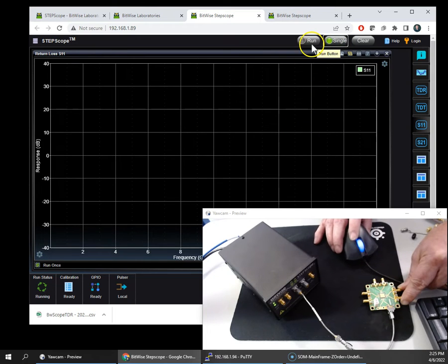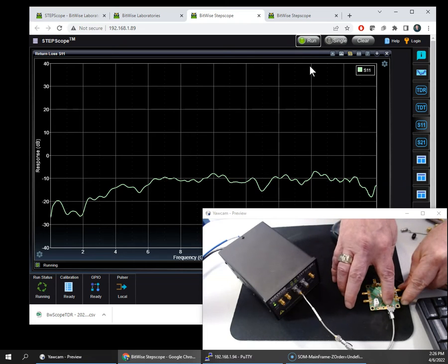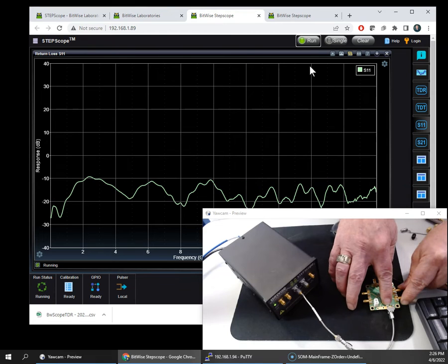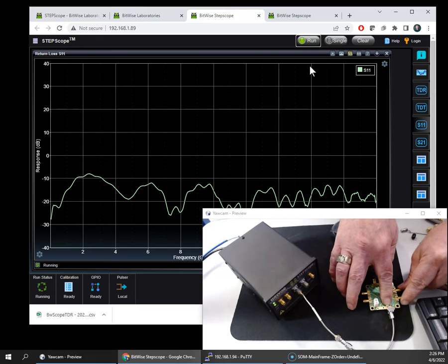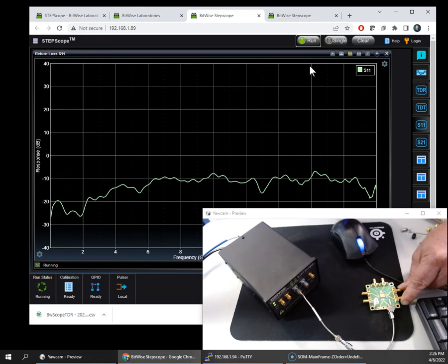This can also run continuously or as a single analysis. And so, for example, let it run continuously. And here I'm seeing the S parameter. If I was to make some deformation into the signal here, I would see that show up in the spectrum as a new S11 response affecting this graph. As I let go, it will go back to what the regular S parameter is. So this is saying I have a 20 dB return loss below 2 gigahertz on this particular application.